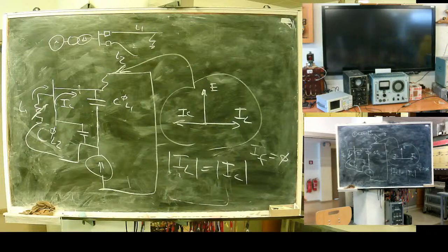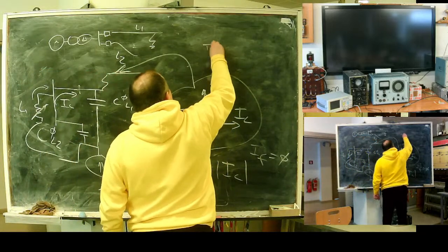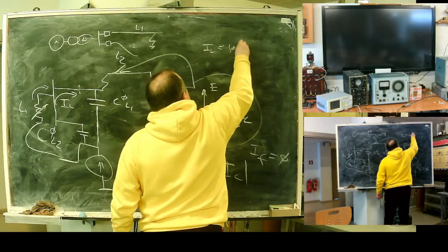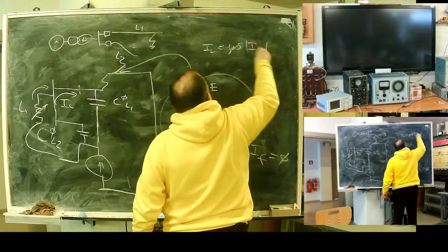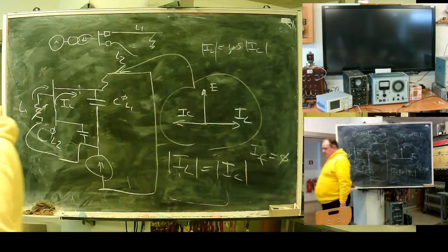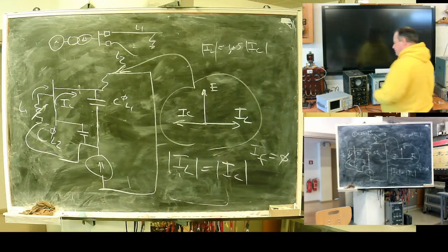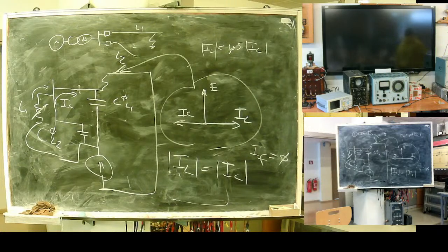Good practice to avoid resonant over voltage is to set IL approximately 1.05 times IC. Bit overcompensate. Petersen coil, or arc coil or arc extinguishing. If you have open overhead line, earth fault appear. In case of compensated neutral, in case you have Petersen coil, current will be 0, arc will deionize in very short time and extinguish. It's very good to, how to say, allow fault to just end.